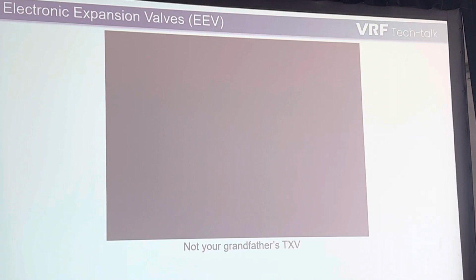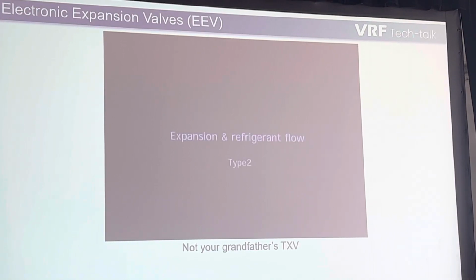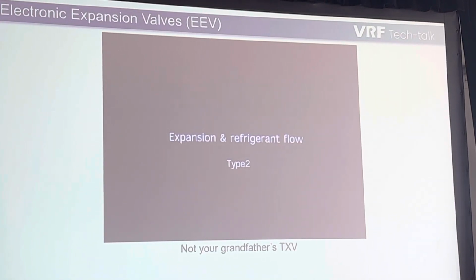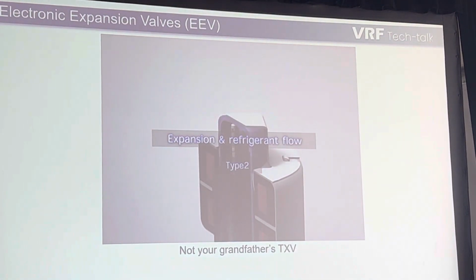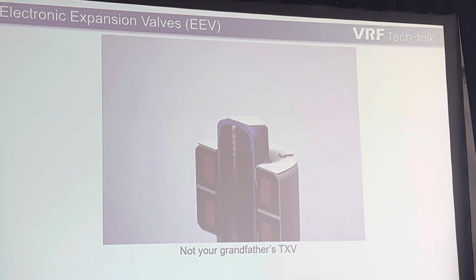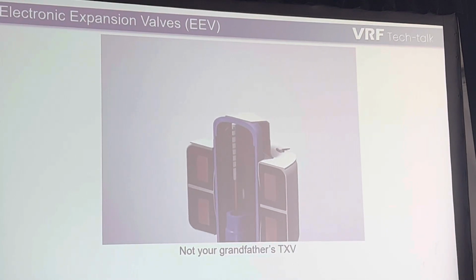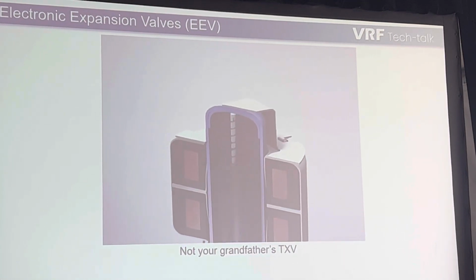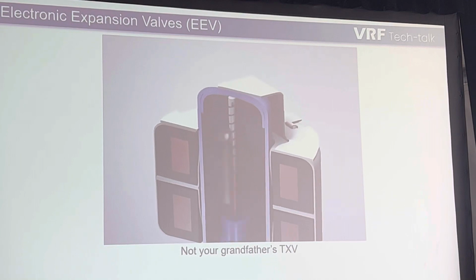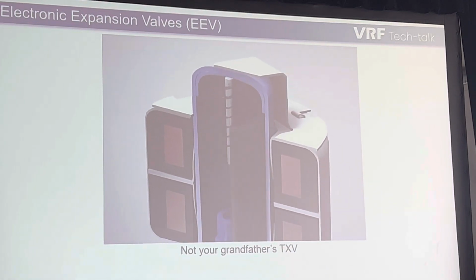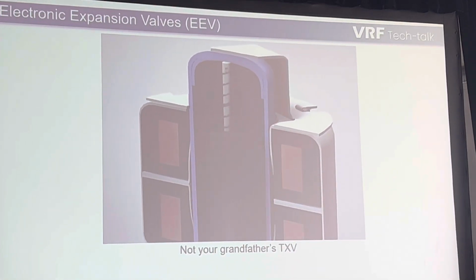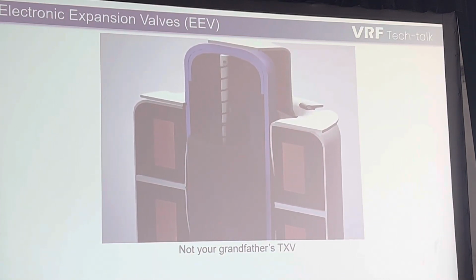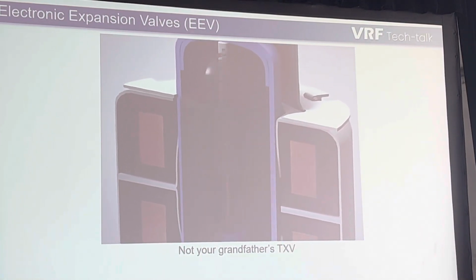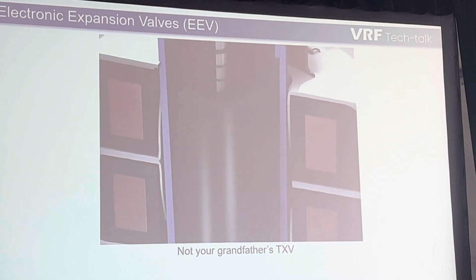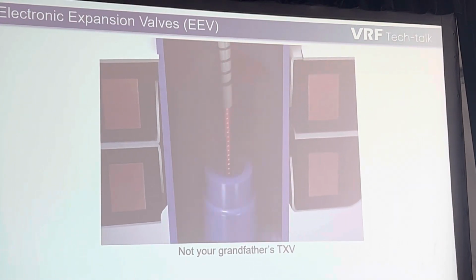It's essentially the same principle, but the thing to remember with these particular types of valves is that when we're servicing them or maintaining them, you're going to want to remove the valve body top off and clean the housing. Rust gets in between them. You'll notice the other one, there's nothing exposed to the weather elements. With this particular type here, if it's not correctly covered, you'll have to go in and do maintenance on it. Otherwise, rust builds up between the outside casing and actually interferes with the magnetic resistance inside the valve, and you won't actually drive the valve like it's supposed to. It'll send the pulses for 480 pulses to open, and it actually only gets 240 pulses of movement because of the rust.